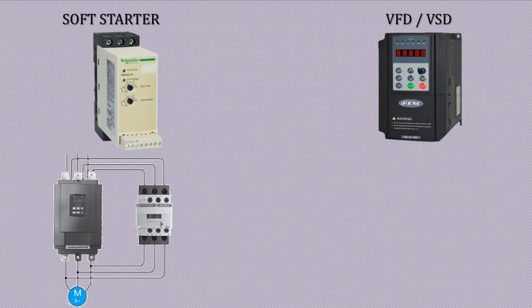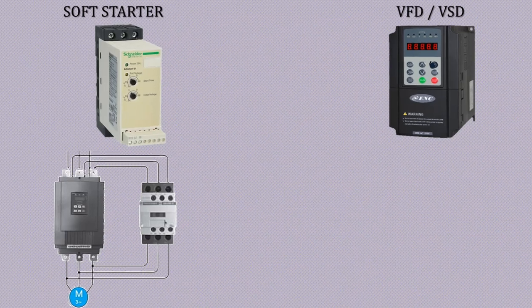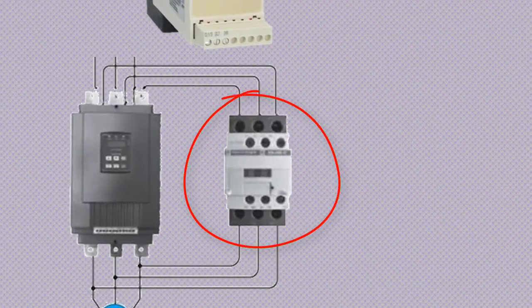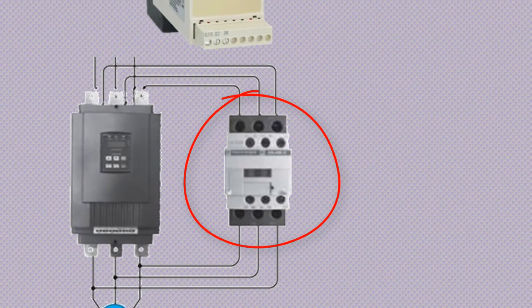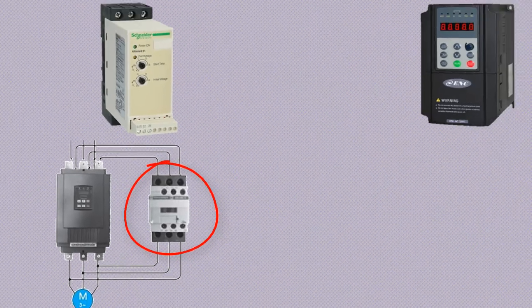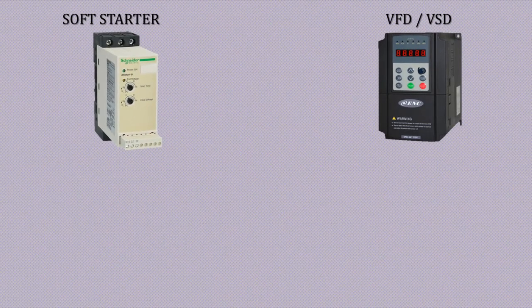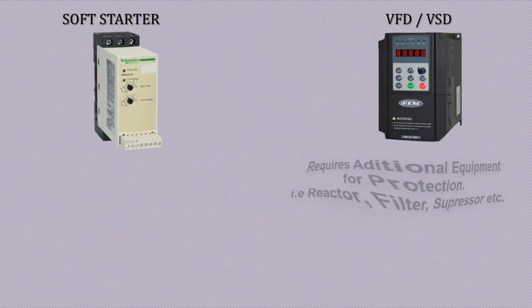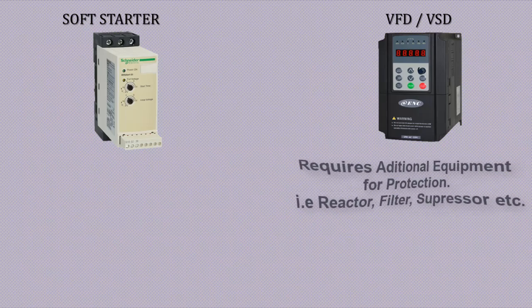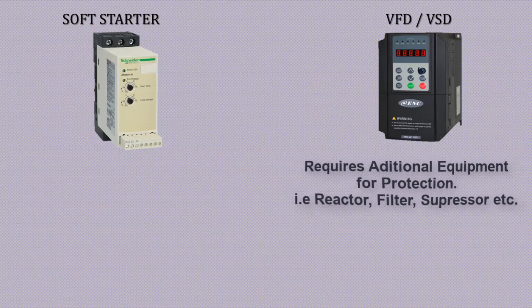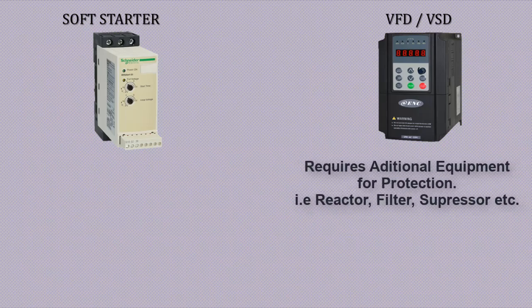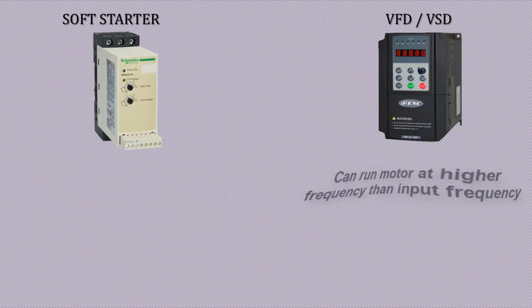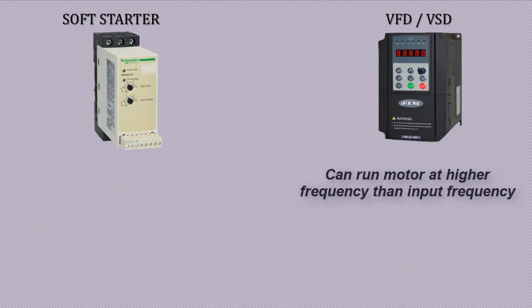Soft starter function ends once rated speed is achieved. This rated speed is maintained through a bypass contactor, hence a bypass contactor is required. While the VFD requires other additional equipment for safety of other electronic equipment, motor as well as VFD itself which will be discussed in next video. And last but more important is VFD can run motor at higher frequency than input grid frequency while soft starter can't provide this feature.